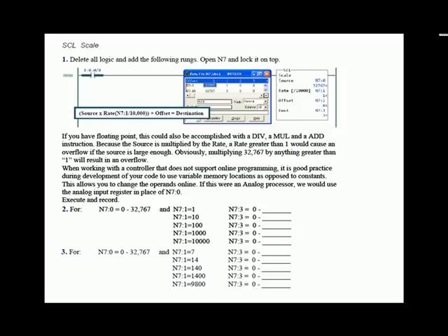The scale instruction, very interesting instruction, very simple once you learn what all of the parameters are in the instruction. You have a source, a rate, an offset, and a destination. I included a little equation that says the source times the rate, which is N7:1 divided by 10,000, plus the offset equals the destination.